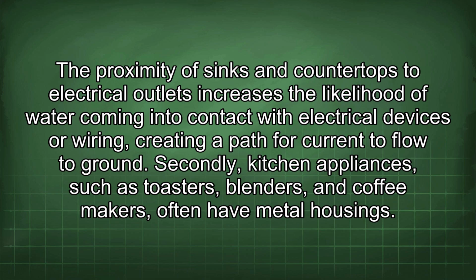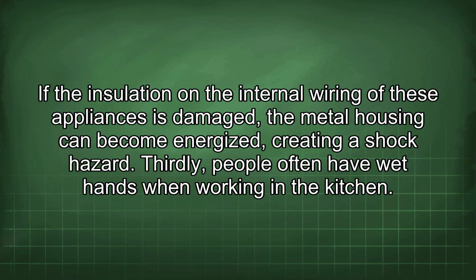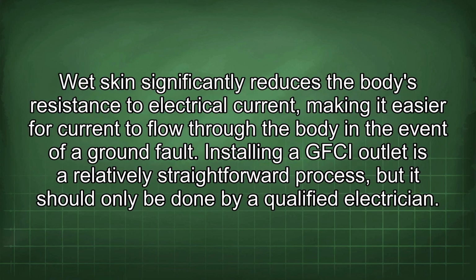Secondly, kitchen appliances, such as toasters, blenders, and coffee makers, often have metal housings. If the insulation on the internal wiring of these appliances is damaged, the metal housing can become energized, creating a shock hazard. Thirdly, people often have wet hands when working in the kitchen. Wet skin significantly reduces the body's resistance to electrical current, making it easier for current to flow through the body in the event of a ground fault.